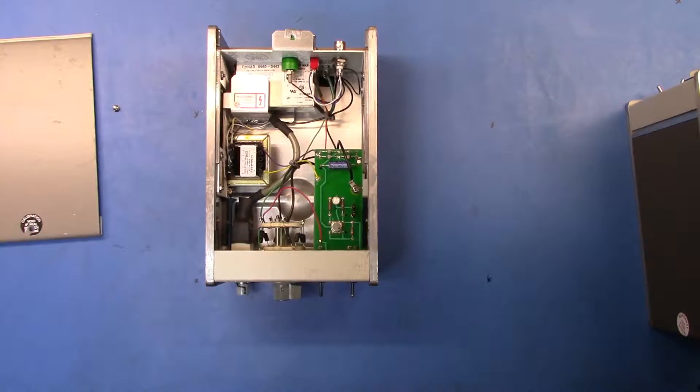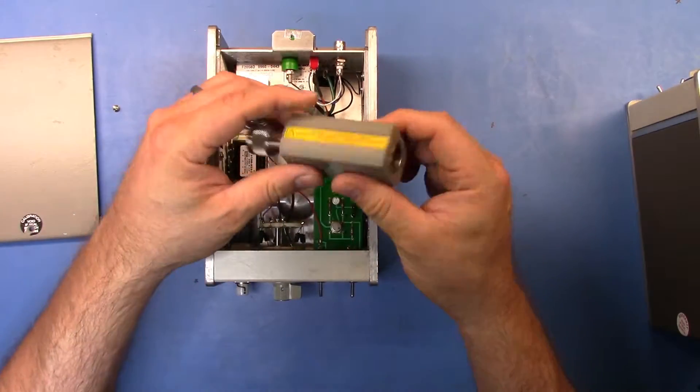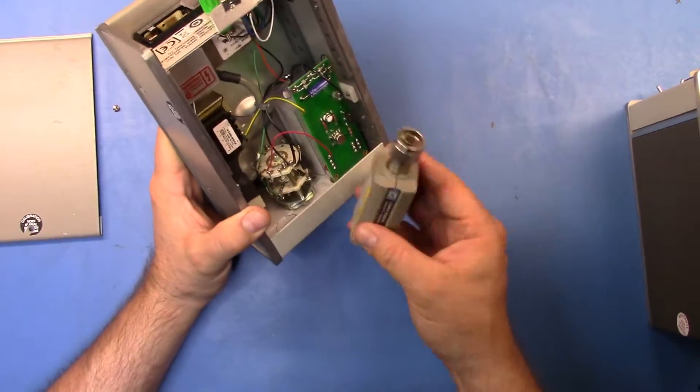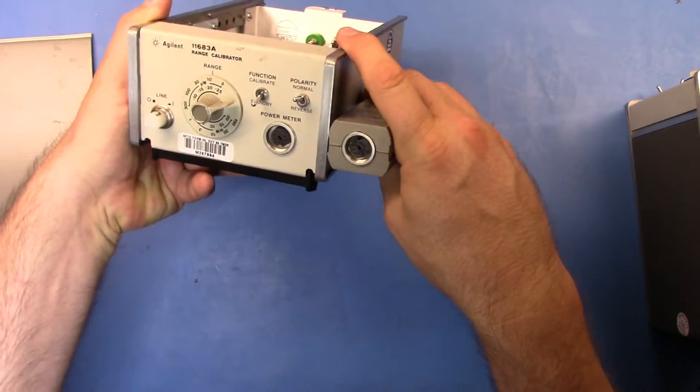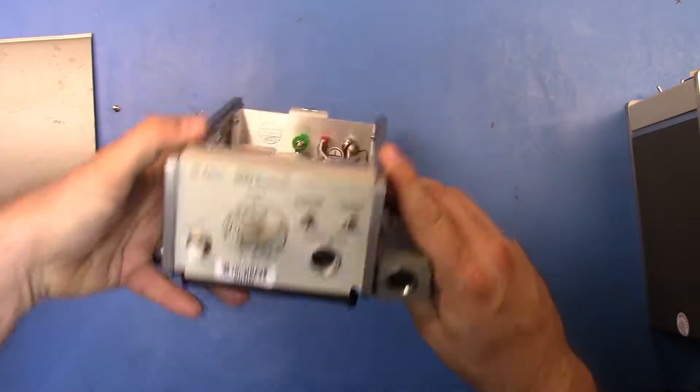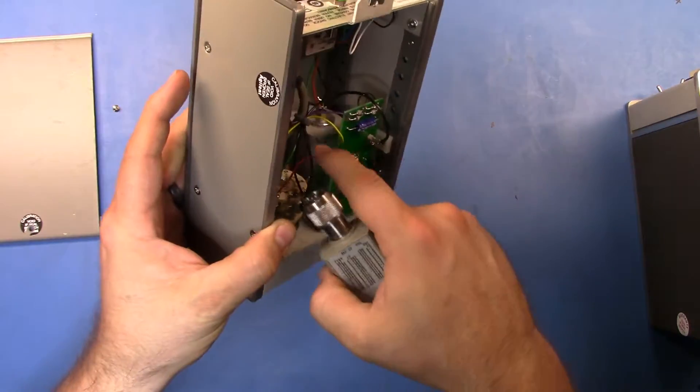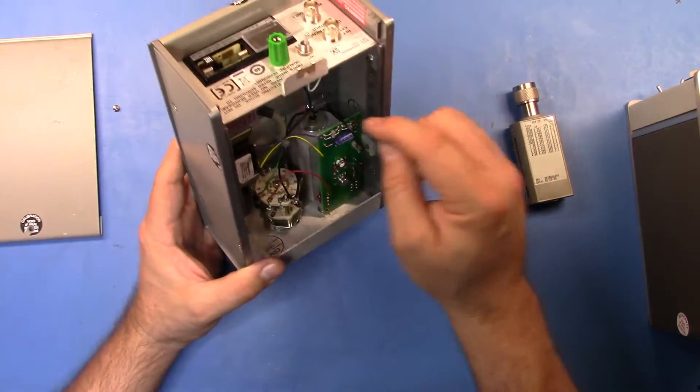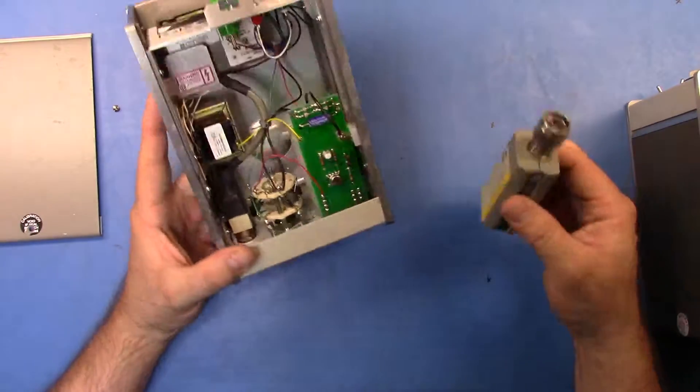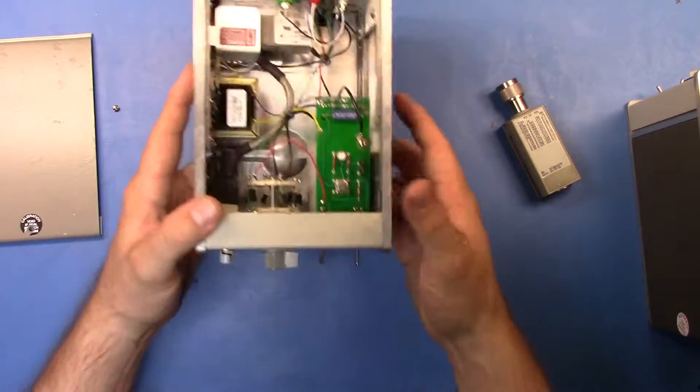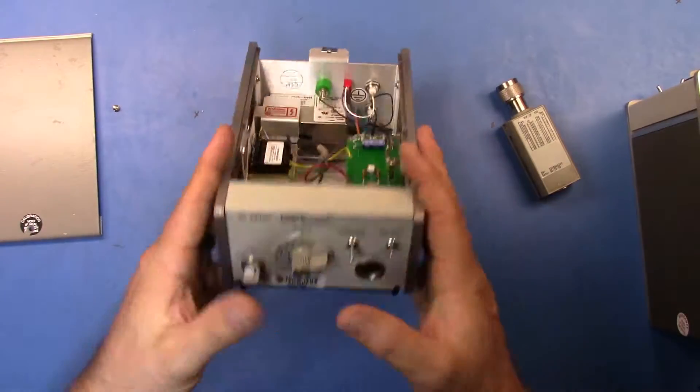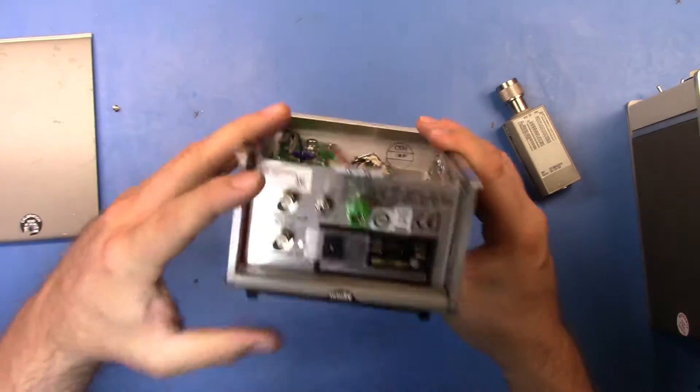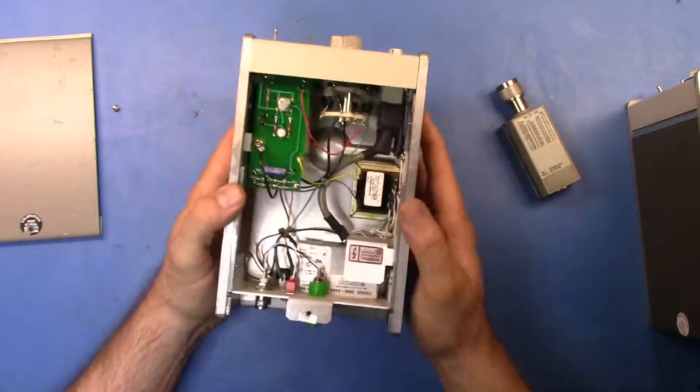That's going to be used to provide the sensor. If you have a look at what one of those guys look like, here is an actual 8482 sensor that I have. You can see that basically what they've done is they've taken that sensor, they've given you the output of the sensor there and the front of the sensor is here. They've removed the actual mounting, the N-type mount there, and they just feed in the voltage directly. So there we go, that's an 11683 range calibrator with the ability to do internal external range calibration.